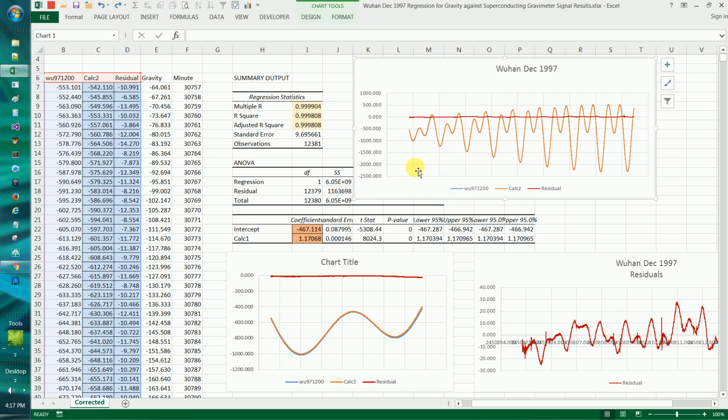So I ran from 2003 to 2013. I ran about a decade of all the superconducting gravimeters. I ran a number of broadband seismometers. The seismometers are so massive an undertaking. I don't remember how many seismometer models I had to go through before I found the ones where I could extract this signal. But it's there, and it's a good means of calibrating, because all you're looking for is an offset and a multiplier. And that sets the scale for that instrument from that point on.